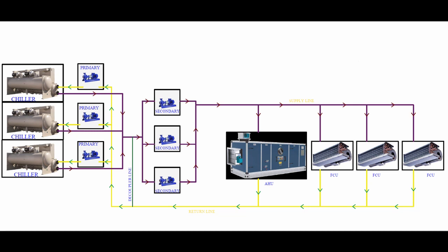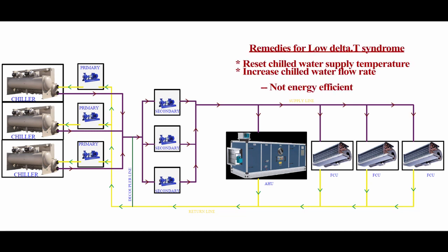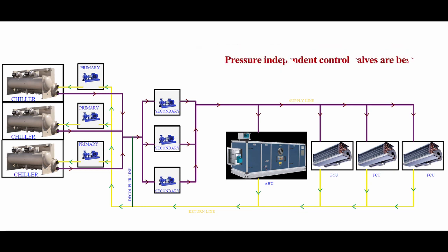By resetting the chilled water supply temperature of the chiller, or by increasing the chilled water flow rate through the chiller, we can avoid low delta T syndrome, but both methods are not energy efficient. Nowadays, we have pressure independent control valves as balancing valves. Irrespective of the difference in differential pressure, they will always give a constant chilled water flow rate. Also, balancing is only required at the beginning. Nowadays, it is more sophisticated by automation.